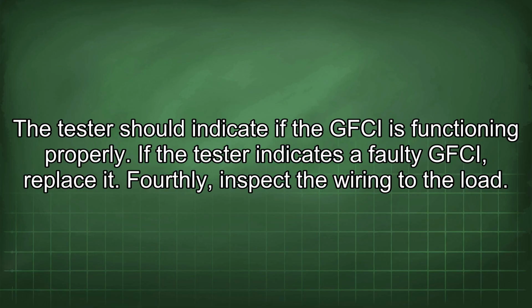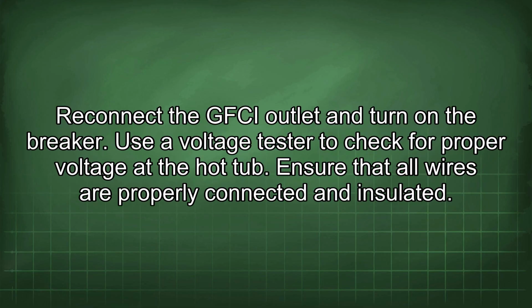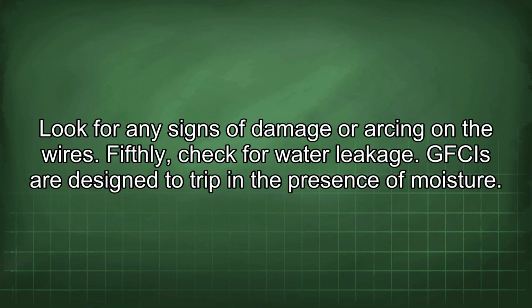Fourthly, inspect the wiring to the load. Reconnect the GFCI outlet and turn on the breaker. Use a voltage tester to check for proper voltage at the hot tub. Ensure that all wires are properly connected and insulated. Look for any signs of damage or arcing on the wires.